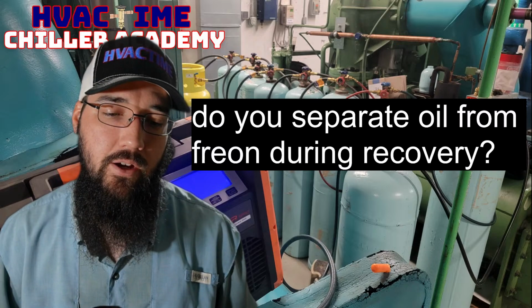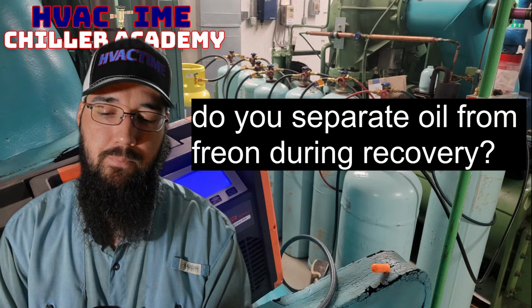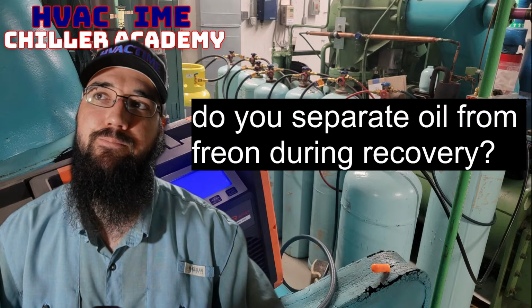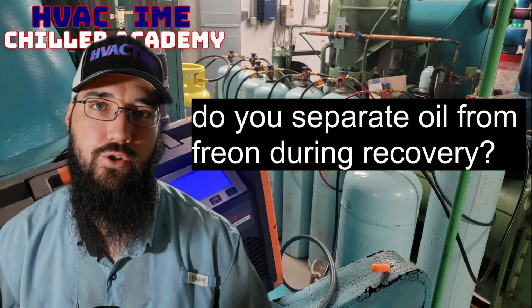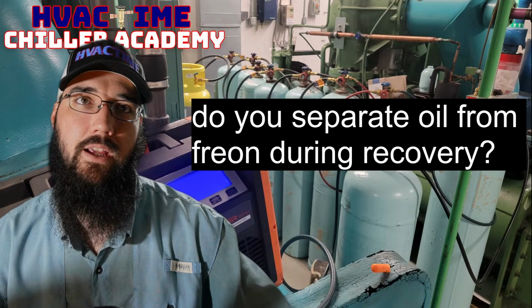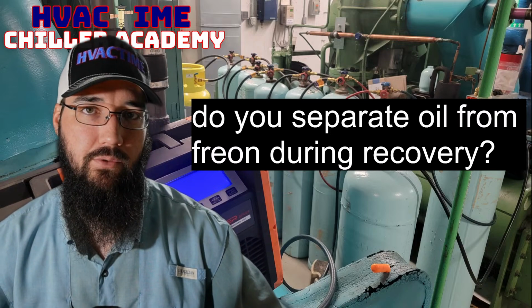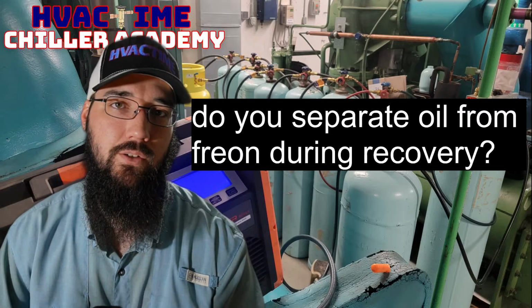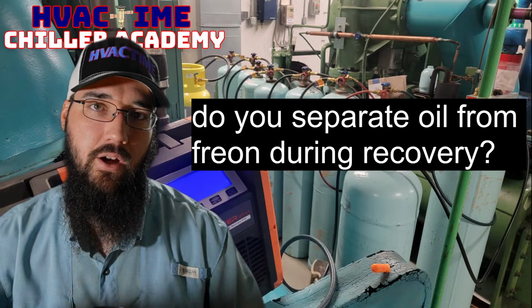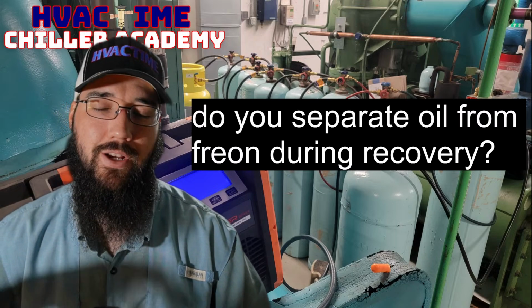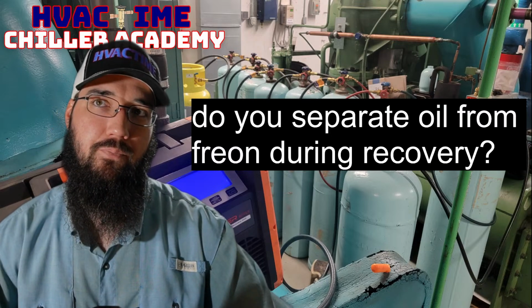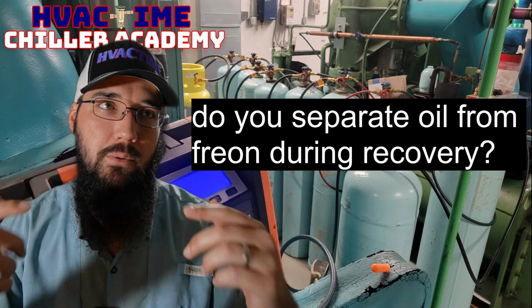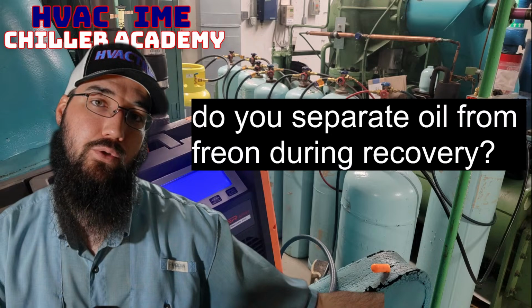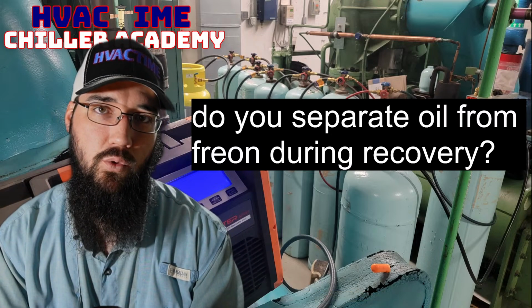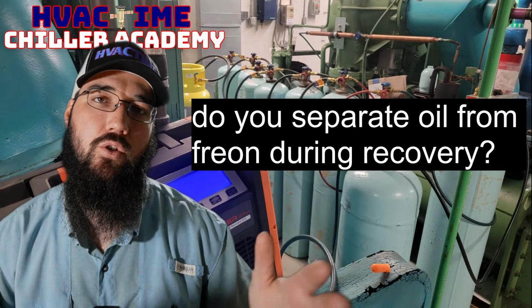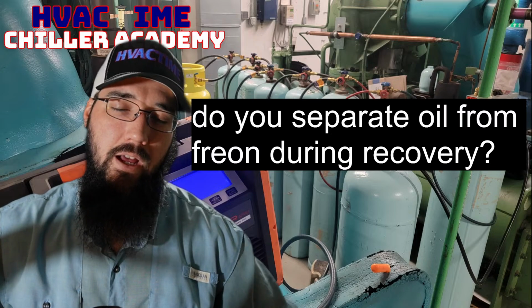A clever thing I heard about recently was, if you have an idea of what your charge should be, waiting until the last, say, 100 pounds or so, basically enough that should fit into one single tank, and then intentionally recovering that portion of the liquid charge into that tank. Instead of doing it haphazardly, which is probably more of what I have done, and then having to mitigate it later, you focus that oil-laden refrigerant into a single cylinder. Then you can charge your other cylinders accordingly, and not have to worry about it as much.